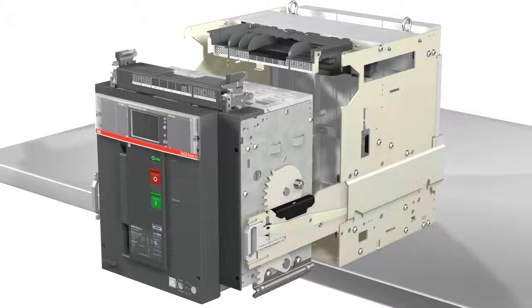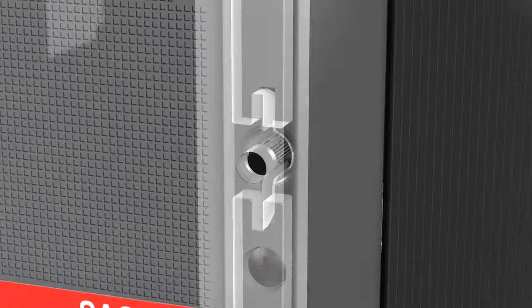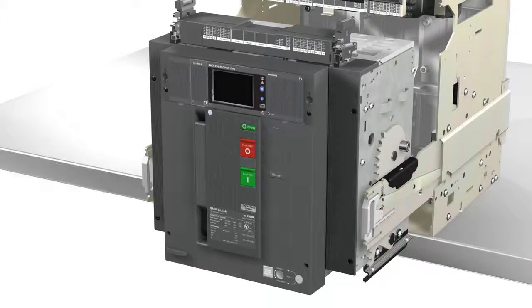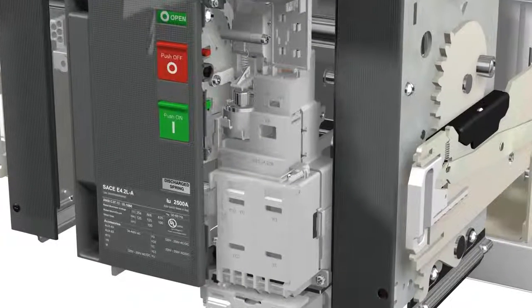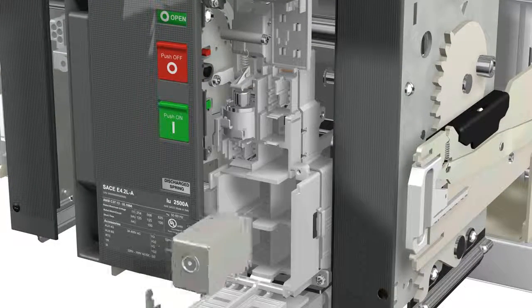The assembly of the electrical accessories of the new SACE Emax 2 air circuit breaker is simple and rapid. Thanks to the wiring always provided with each circuit breaker, it is only required to insert the accessory in the proper slot and to connect it in the terminal box through push-in terminals without any external tool.